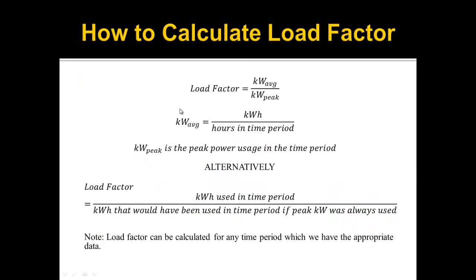We haven't learned how to calculate load factor yet, so let's look at how to calculate it. There are a couple different formulas. Load factor equals kilowatt average divided by kilowatt peak. To get kilowatt average, you take how many kilowatt hours you used in a time period and divide by the hours in that time period. Kilowatt peak is the peak power usage in the time period. You're going to be doing this monthly in your task.